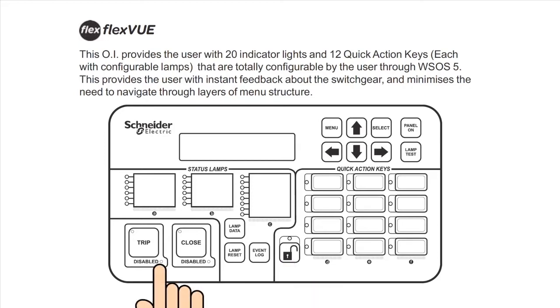Enable or disable trip switch disables the trip key. When the switch is in the disable position, the trip coil in the recloser is electrically disconnected from the control electronics. Thus, the switch provides a physical isolation point for the control circuitry. The recloser cannot be opened, an audible alarm in the panel will sound, and the disabled lamp in the trip key will flash. The trip key operates normally when the switch is in the enable position.